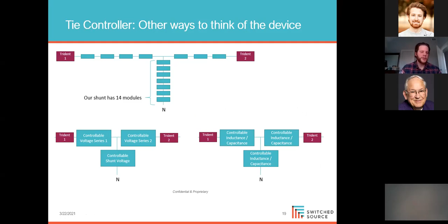We worked with a top tier manufacturer for our power electronics builds. So what you have here is a cold plate, IGBTs, gate driver boards on top of them. You have a local voltage supply board and a communications board stacked on top of this. These are our capacitors. Because we're more of a per-phase device, as opposed to a 3-phase device with a common DC bus where things are expected to be very balanced, there's a decent amount of ripple, and your capacitors get pretty big.